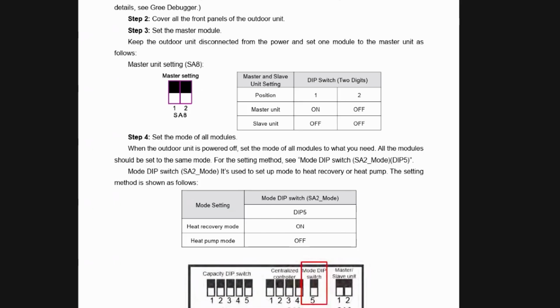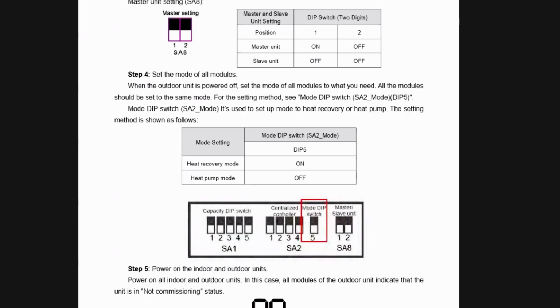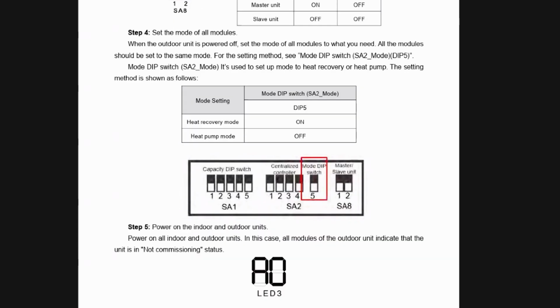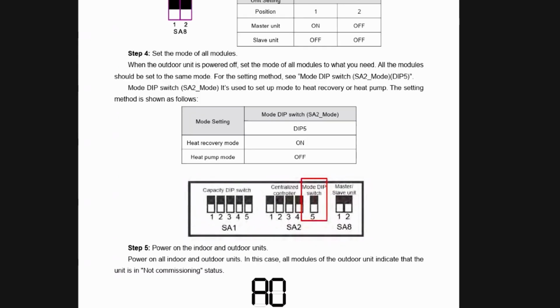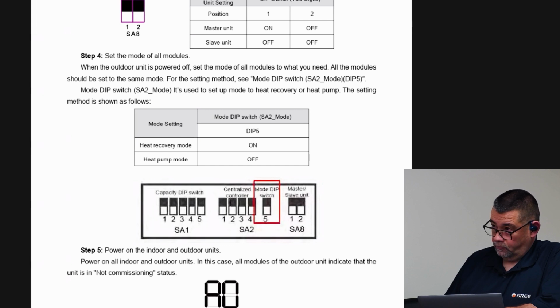So we want to go to the service manual. This applies to those situations where you're going to change that outdoor unit from a heat pump to a heat recovery. That is this switch here, switch number 5, where we change that dip switch to either on or off. Correct. For heat recovery mode it's on, and for the heat pump it is off. In my opinion, these are important checks. You need to make sure that machine is set up the way you need it to work, whether heat pump or heat recovery, knowing that it can do either. It should be one of those off the checklist.